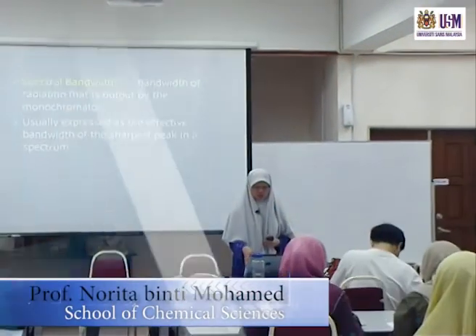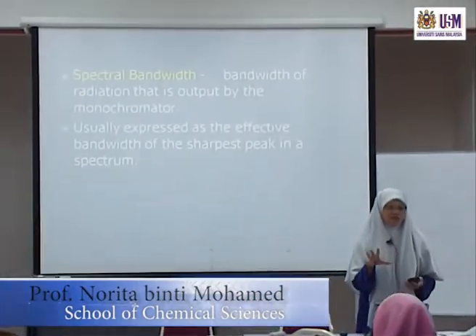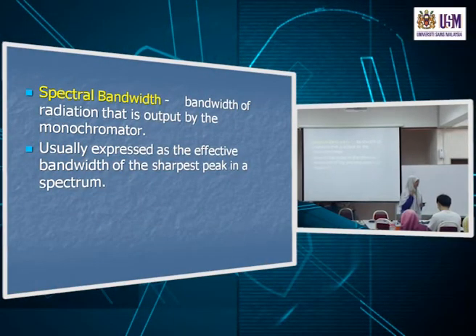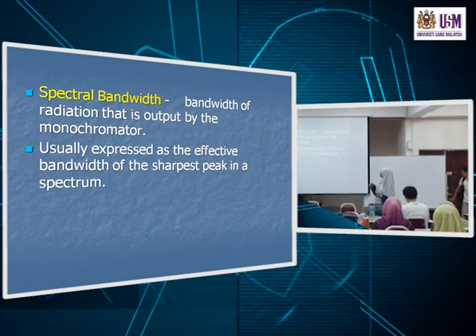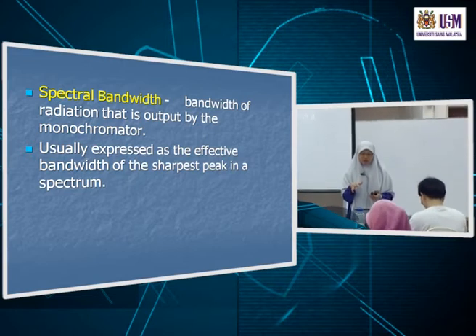What we last looked at was the performance of a monochromator, and this is the last aspect — the quality of radiation that comes out. One of the things we are going to talk about is spectral bandwidth: the bandwidth of radiation that is output by the monochromator.